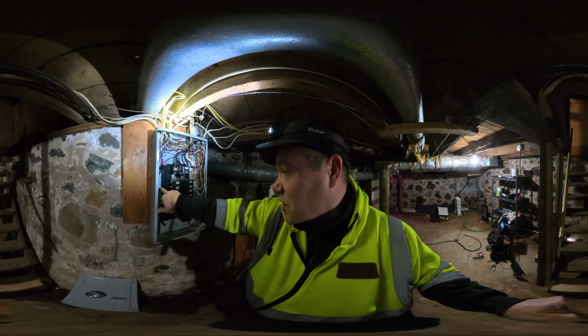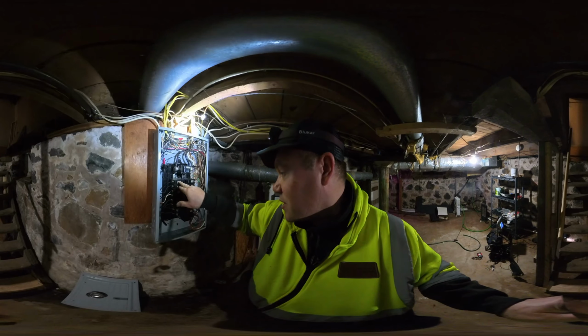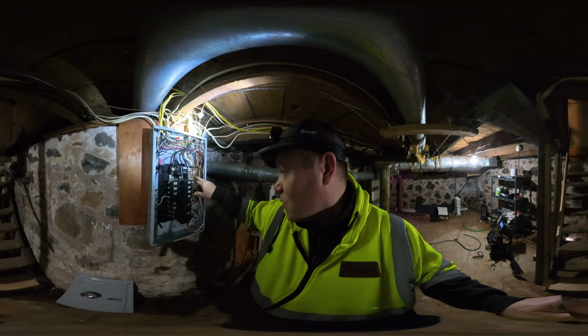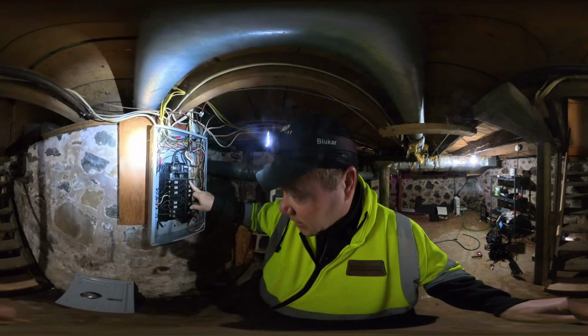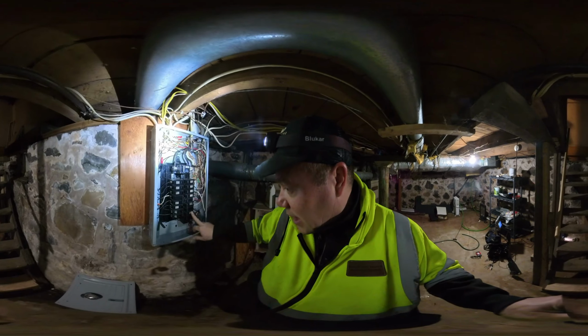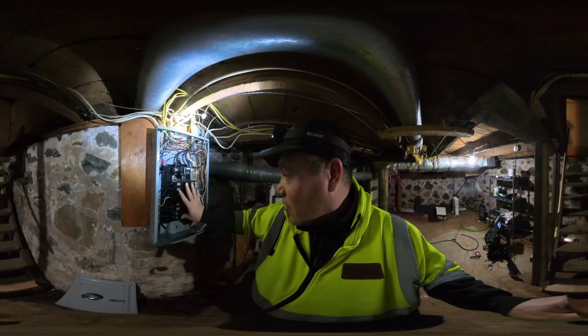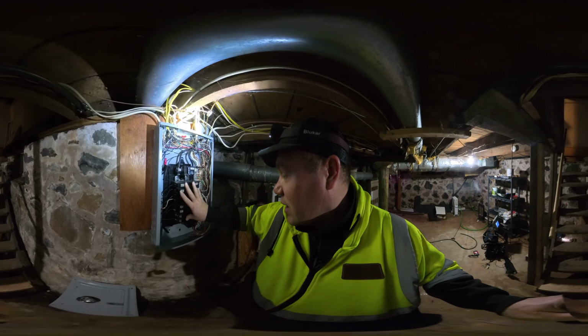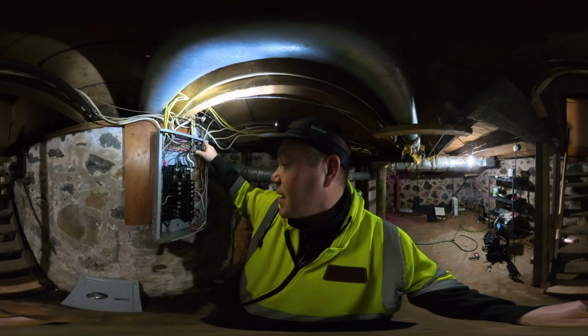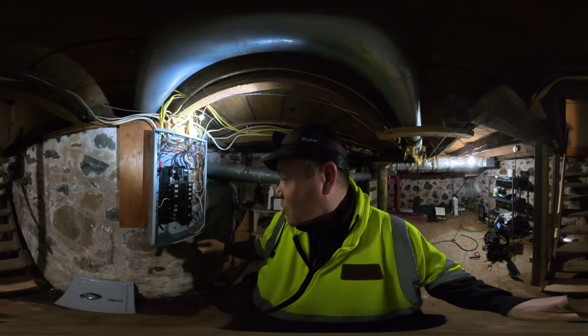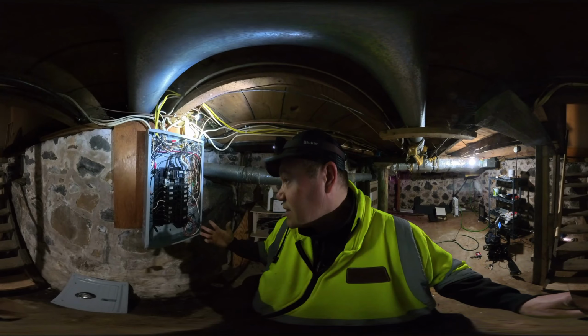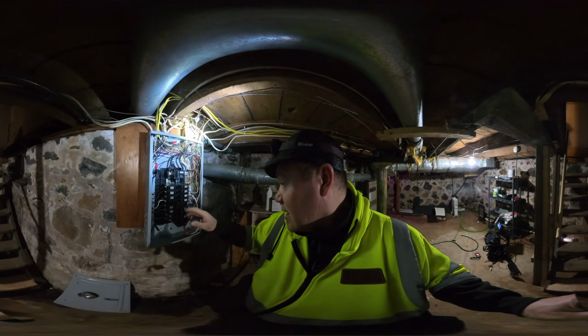I'm okay with the larger conductor going into the breaker because the breaker is going to pop, but a smaller conductor going into a larger breaker is where I have a problem. Nonetheless, with the system we have currently, being 100 amp and properly bonded, the electrical going in doesn't look like it was done by an amateur.